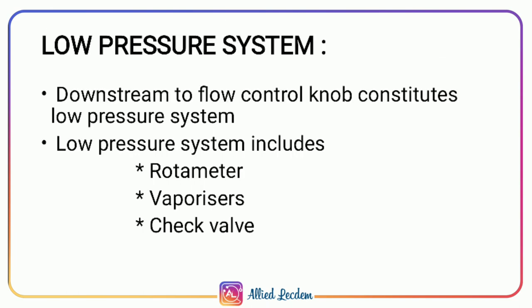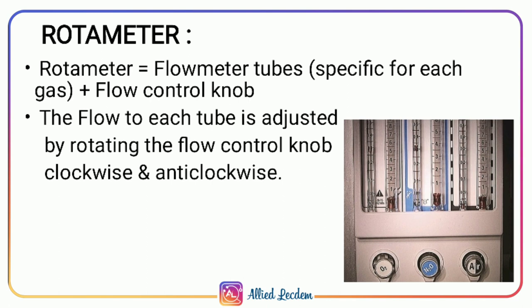The low pressure system consists of gas downstream from the flow control knob and includes the rotameter, vaporizers, and check valve. The rotameter consists of flowmeter tubes with flow control knobs, and they are specific to each gas. To increase the flow, the knob is rotated anti-clockwise; to decrease the flow, the knob is rotated clockwise.